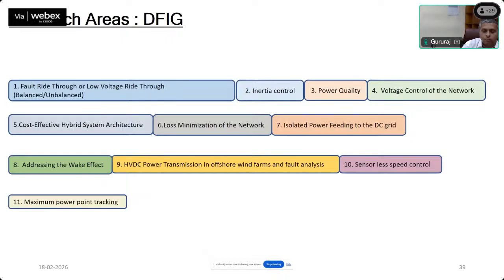For loss minimization of the network, system losses can to a certain extent be minimized by adjusting the reactive power flow. Because we have back-to-back converters with the double fed induction machine, reactive power compensation can be well achieved.